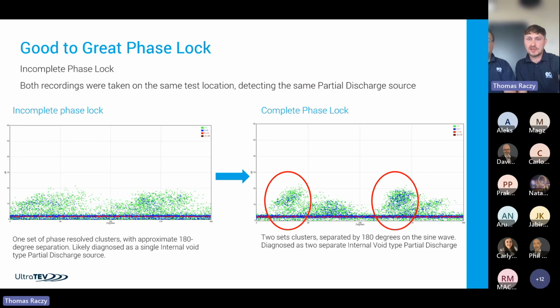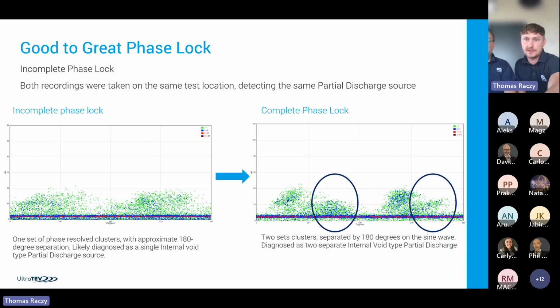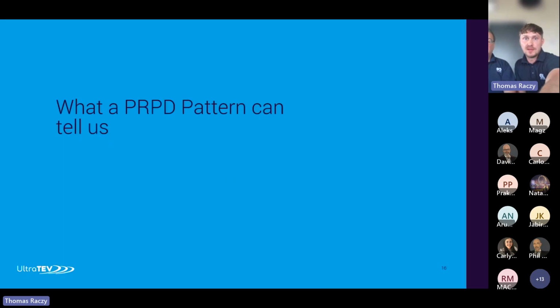From that, we can see that we clearly have two defined sets of clusters. The first set of clusters, from one source of discharge, is highlighted with the red circles, and the other cluster with the dark blue circles. So you can see that correct phase lock has now enabled us to correctly analyze that there are two separate sources of discharges, most likely on two separate phases.